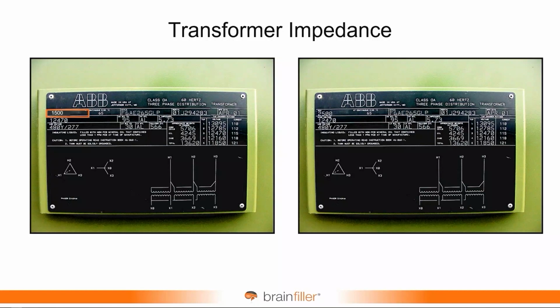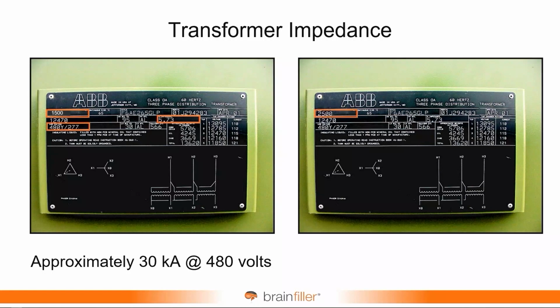Transformer impedance. We have a 1500 kVA transformer on the left, using the impedance and the secondary voltage. The fault current on the secondary would be in the neighborhood of 30,000 amps at 480 volts, maybe a little more, maybe a little less, but in the ballpark of 30,000 amps. If that transformer size is increased, then the fault current would also increase to 50,000 amps. Could that affect the incident energy? Absolutely. As the fault current goes up, assuming the arc duration is the same for each case, then 50,000 amps would lead to a larger incident energy.